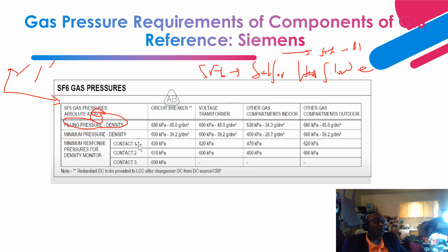So at the time that you are filling the SF6 gas, let's say if you have an SF6 gas leak, you use that chart that the manufacturer provides as part of the instruction manual. Based on the ambient temperature at the time that you are filling, you determine the pressure that you are supposed to fill the GIS to. The pressure is scaled based on the ambient temperature at that time. So it gives you the filling pressure, which is the maximum, and the minimum pressure.